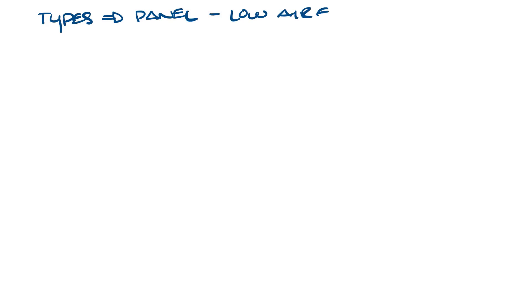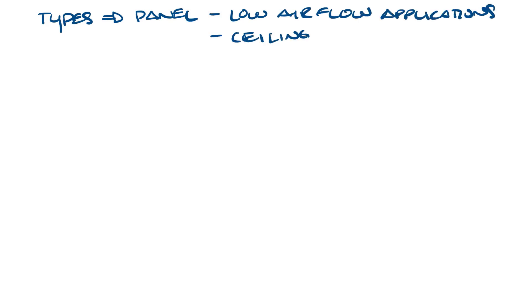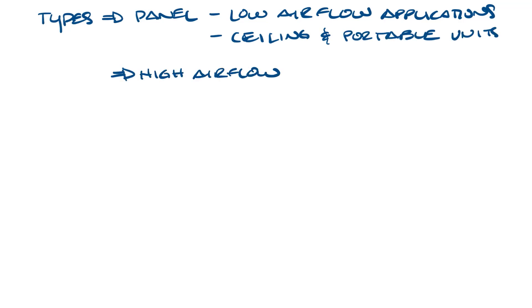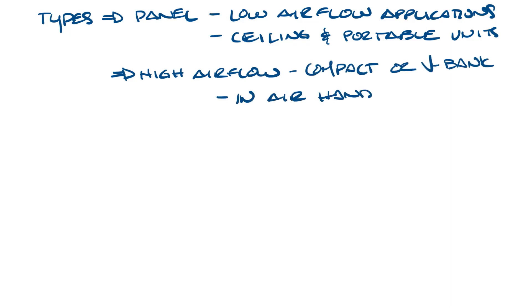There are a couple different types of HEPA filters. There are panel filters, which are used in low airflow applications — for example, you would see these in ceiling applications or portable HEPA units. Next, you have high airflow HEPAs, often referred to as compact or V-bank HEPA filters. You'll see these in air handlers.